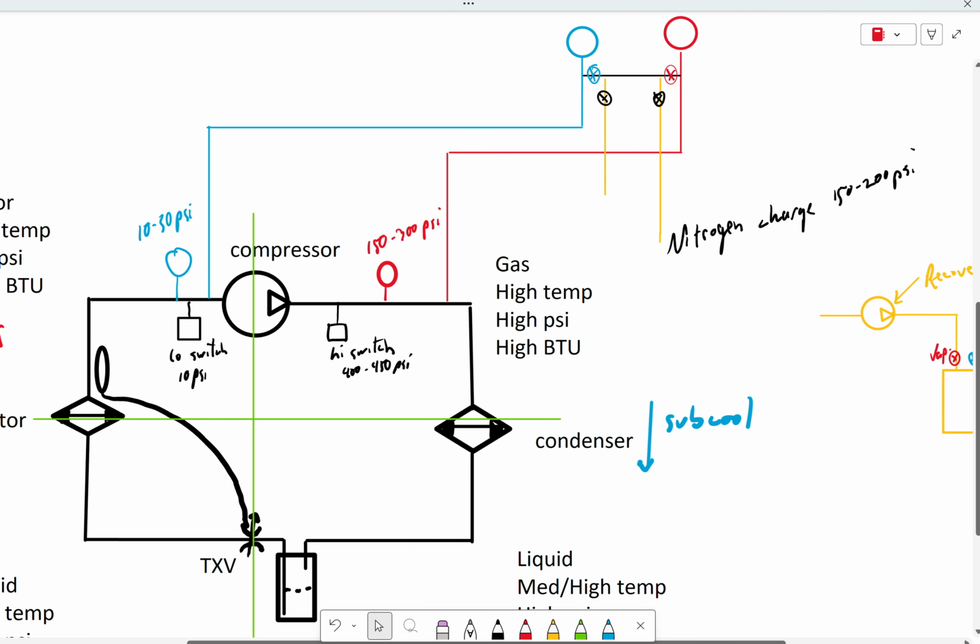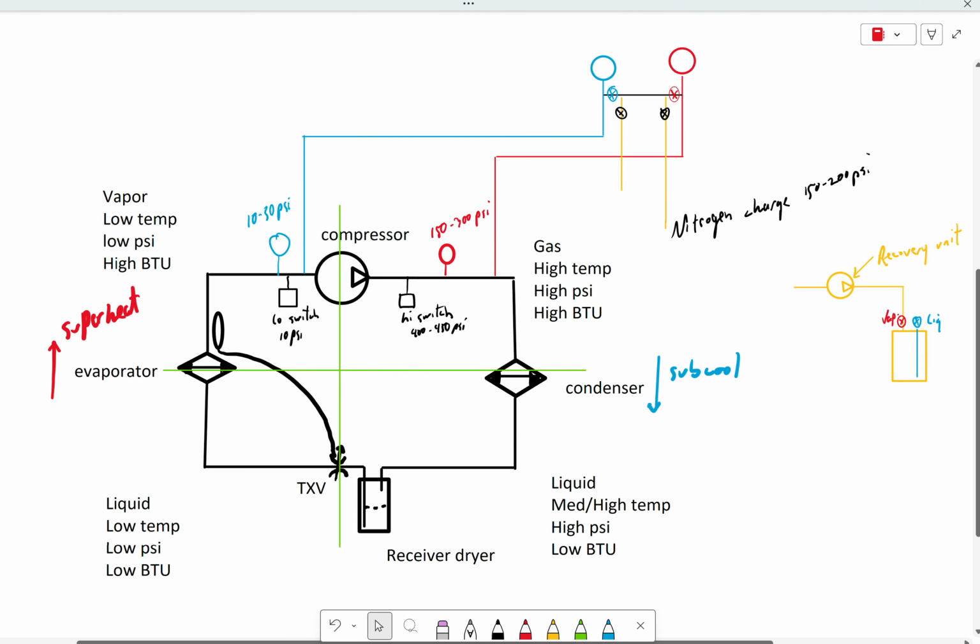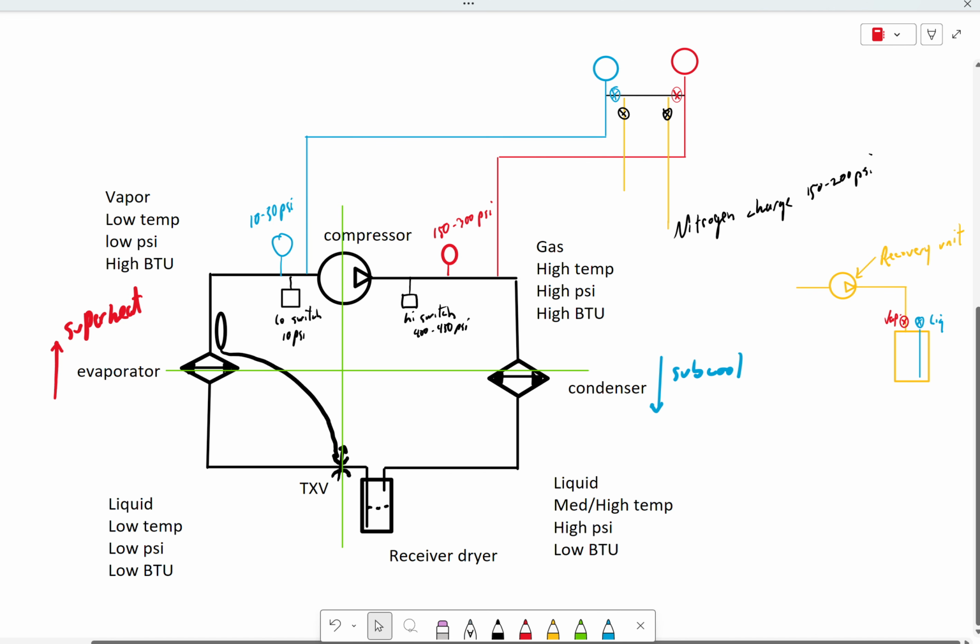Now, a standing nitrogen pressure leak test, if you look back through the regulations that you were taught when you were doing your MOPIA training, I would have said a minimum of 150 psi for a minimum of either 15 or 20 minutes has to hold for it to be considered to have passed a leak test. I've worked on machines where they did pass the leak test according to that, and then you still get a call 2 weeks later that the thing's not working again, right? And that sucks. That means there's obviously a pinhole leak that you didn't find. So how do you find that?